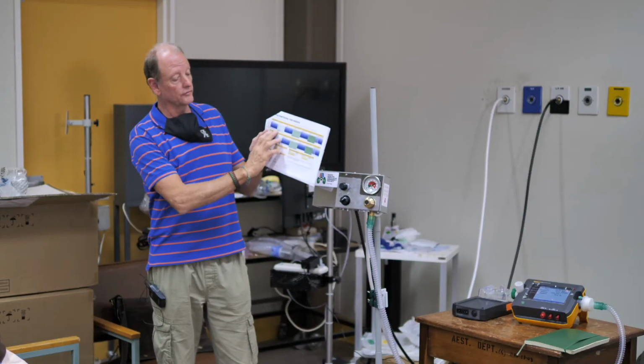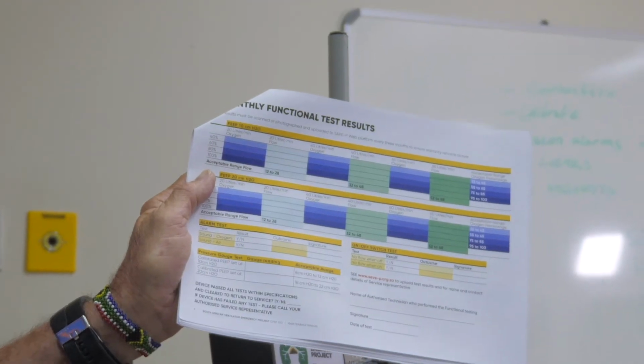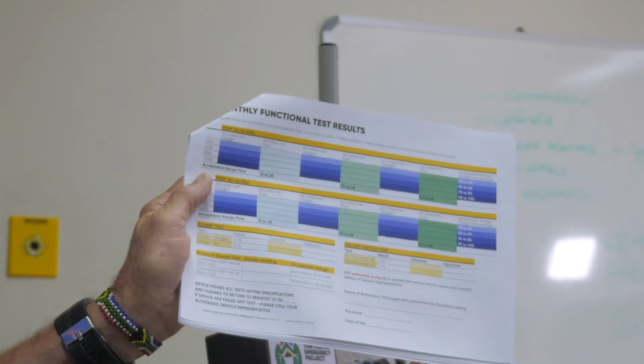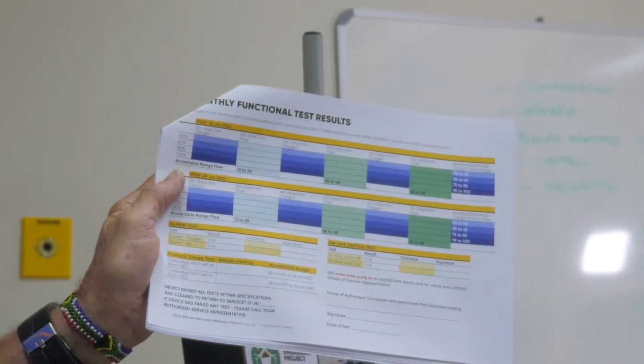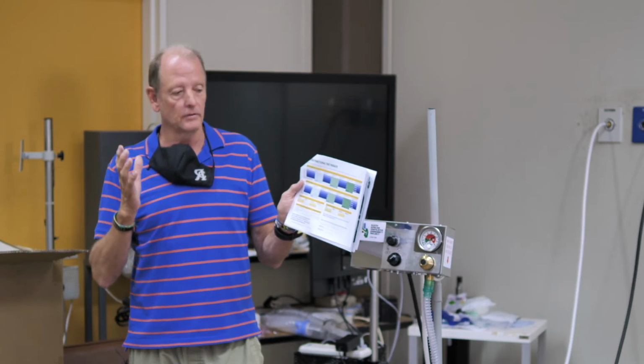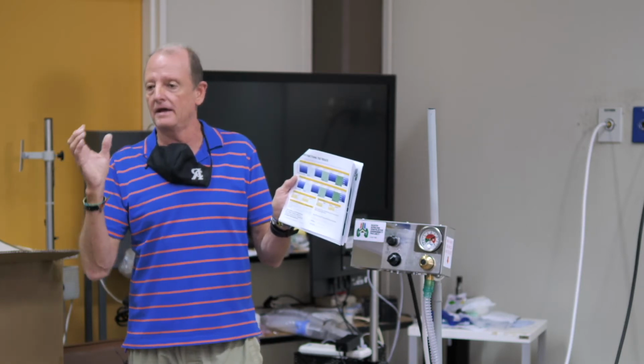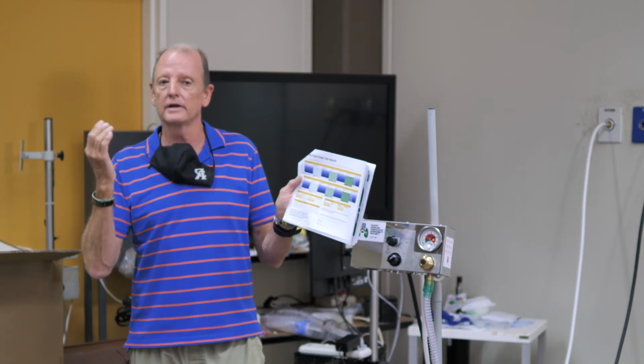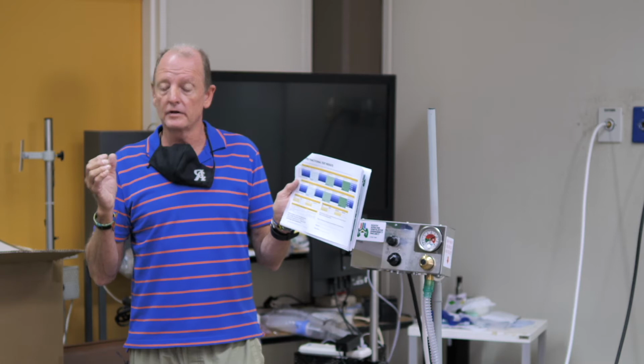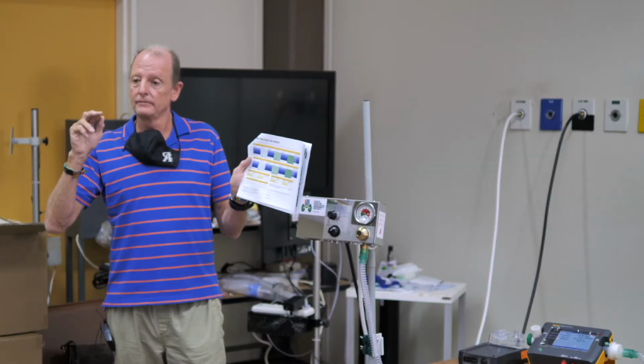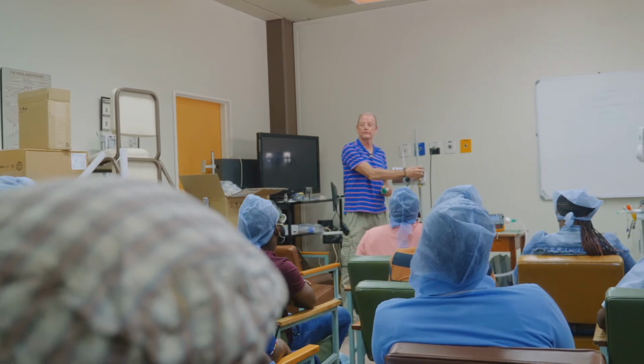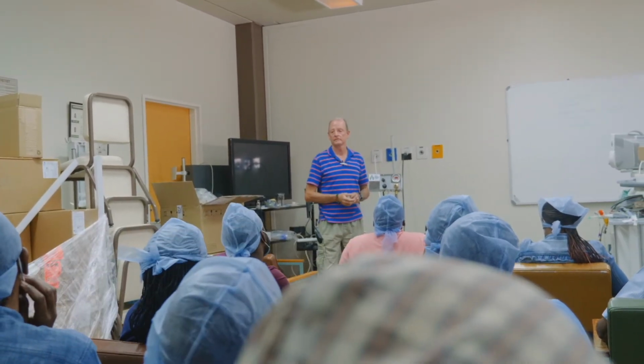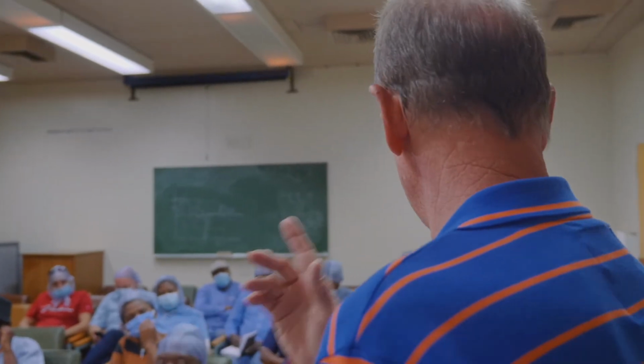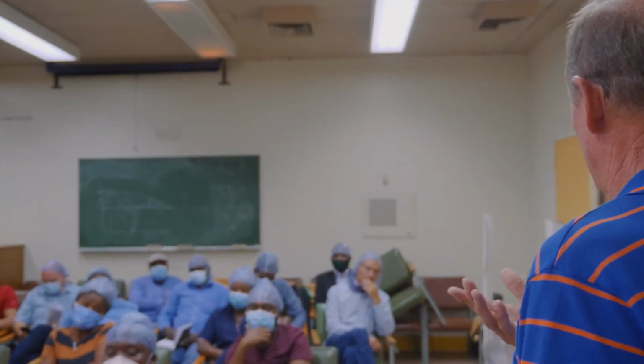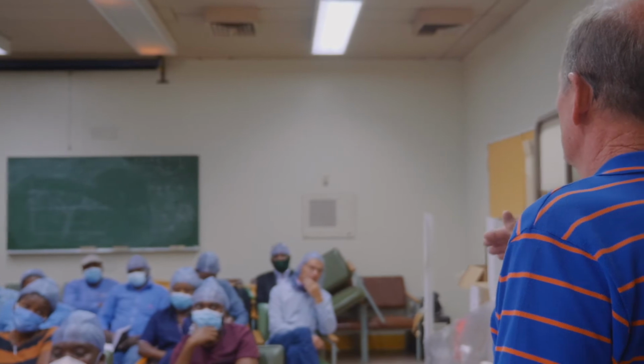And down here it gives you your specs, your flow rates and the tolerance that you should be in. Your tolerances are down the bottom. If it is out of tolerance, don't try and fiddle with it. You've got to get the flow rate and the blender readjusted to bring it back well within the calibration. Because believe me, a slight twist on the control knob, if you force it, like some people really want to, you will damage that spindle. It's just a needle valve. That's all it is, a brass needle valve. So just handle it with care.